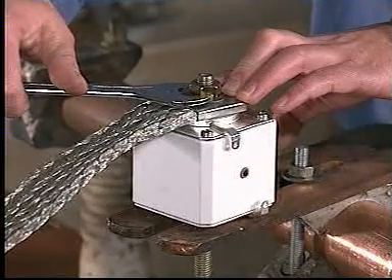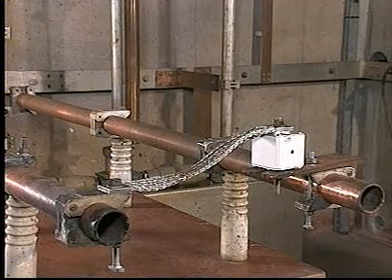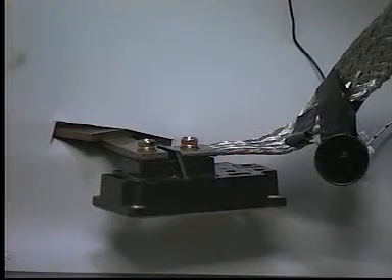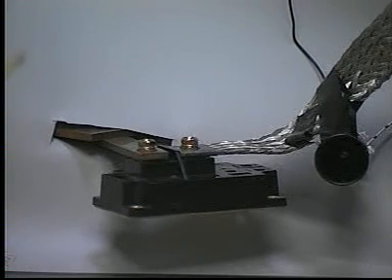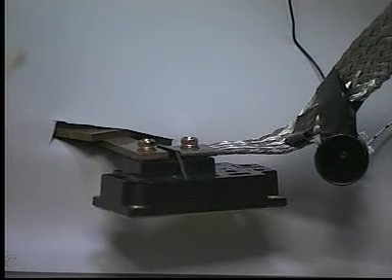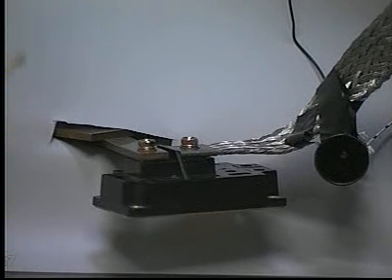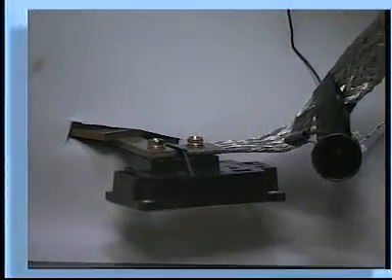The second test shows the same circuit conditions, with the only difference being the addition of an ultra-current limiting semiconductor fuse. While the fuse is unable to protect the functionality of the IGBT, it is able to at least provide Type 1 protection, such that the ionized products are contained within the IGBT housing. In this way, adjacent circuit components are not exposed to explosive end-of-life scenarios.